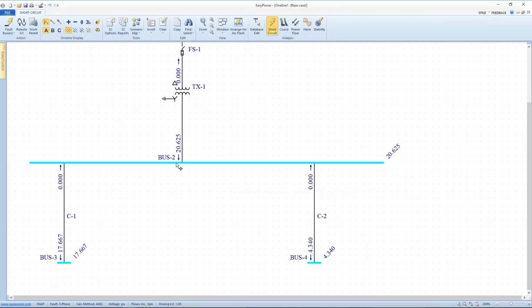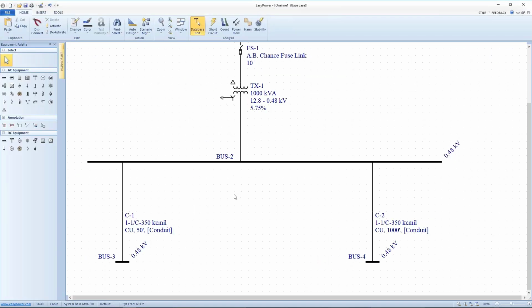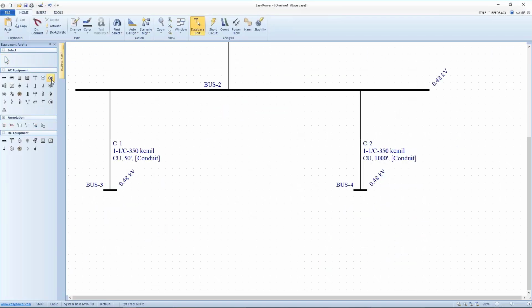What this is telling me is, if bus 2 has a balanced three-phase fault, what's referred to as a bolted fault, each phase will see 20,625 amps, 20,625 amps per phase. If this bus faults, bus 3, we'll see 17,667 amps. Now, in this particular conversation, he was not showing any downhole loads. In reality, he'd be showing what the downhole pump motor was contributing. So I'm going to save this and make that addition to the conversation.